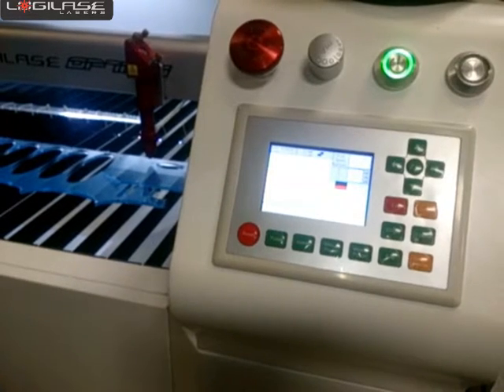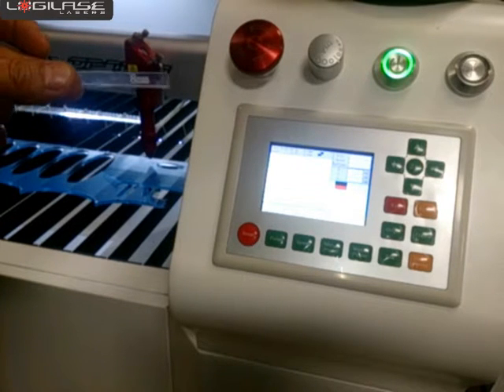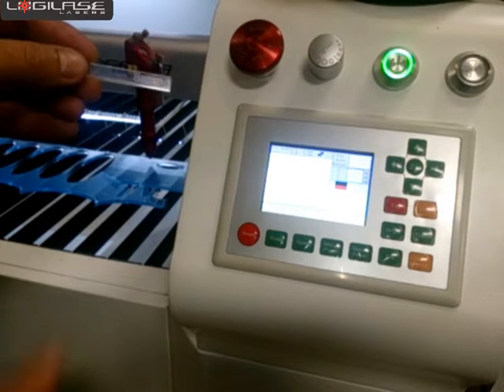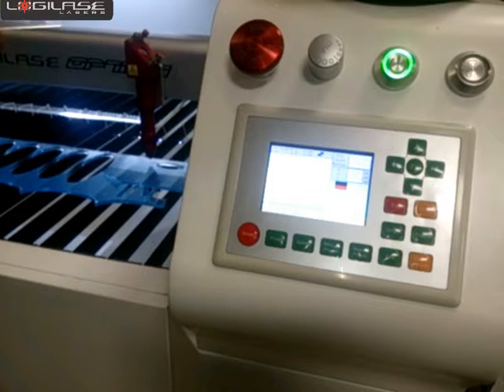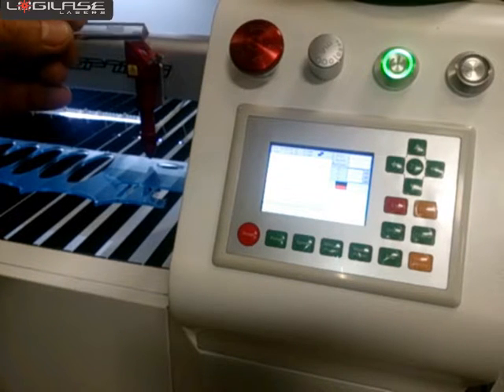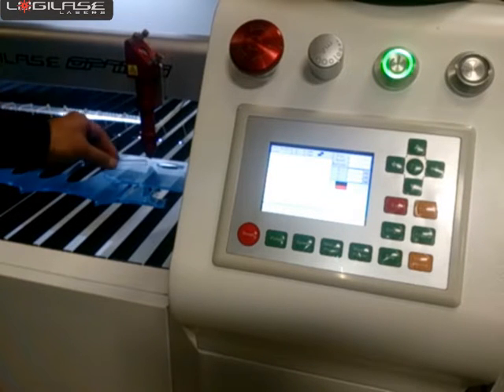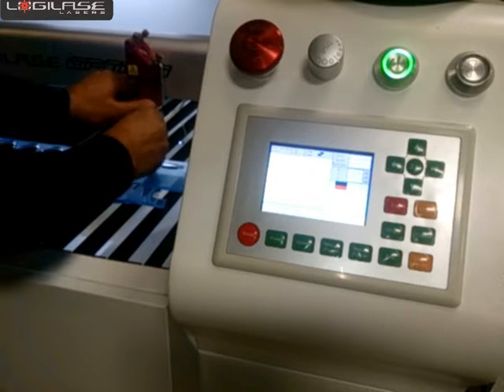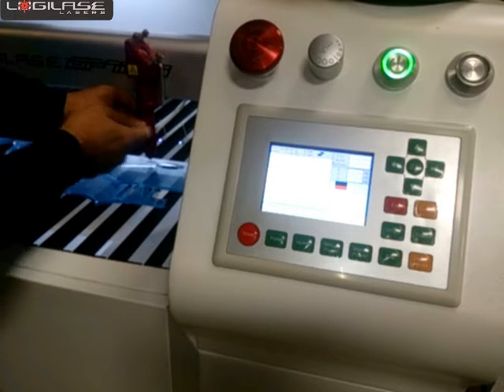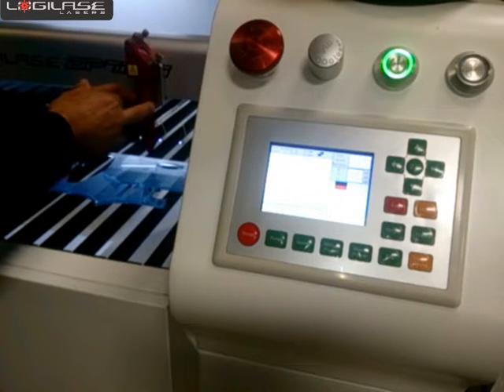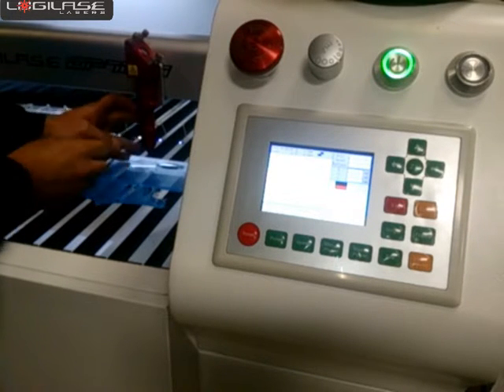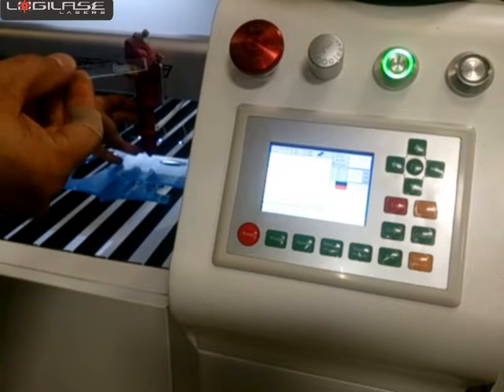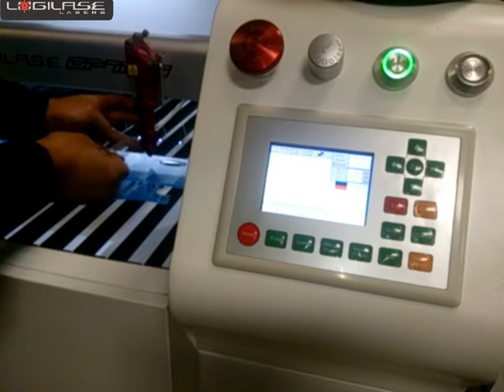But for manual adjustment, which is our case here, for focusing, we have to use the plastic template, which comes with all types of machines. It shows here, usually it's 8 millimeter for this type of machine and 2.5 inch lenses. So the process is simple. You can just release the lens tube here by loosening the thumb screw, and then place the plastic template facing this 8 millimeter towards you.